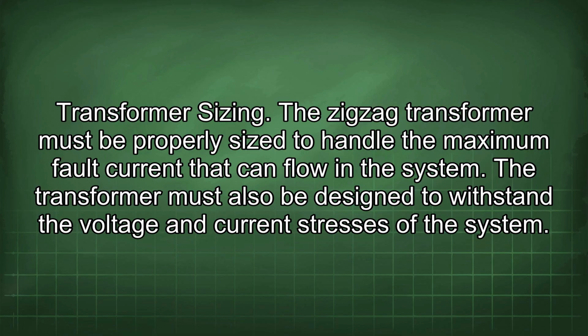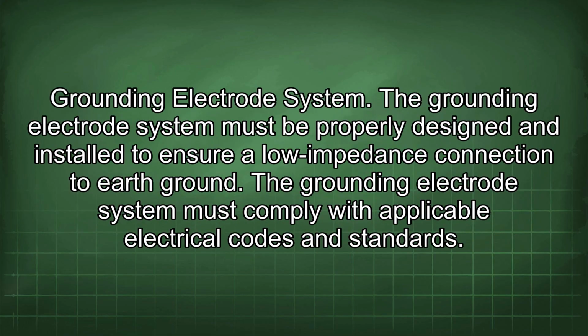Transformer sizing. The zigzag transformer must be properly sized to handle the maximum fault current that can flow in the system. The transformer must also be designed to withstand the voltage and current stresses of the system. Grounding electrode system. The grounding electrode system must be properly designed and installed to ensure a low impedance connection to earth ground.